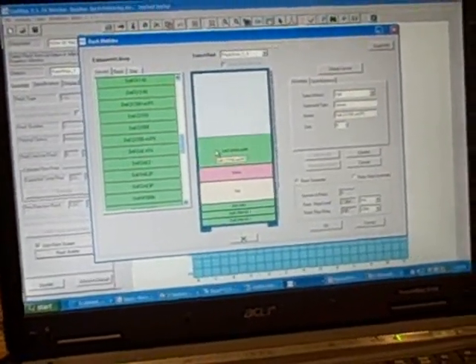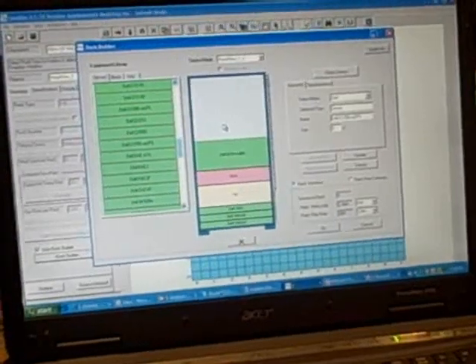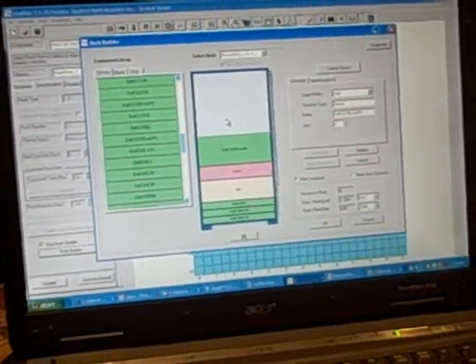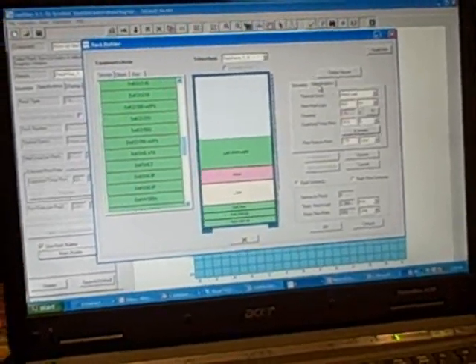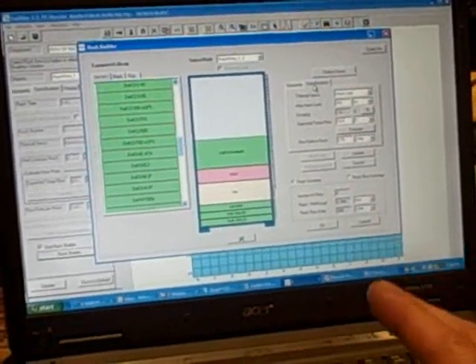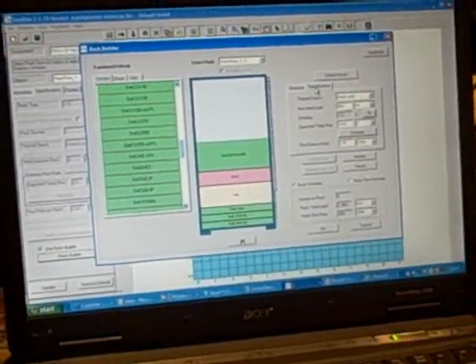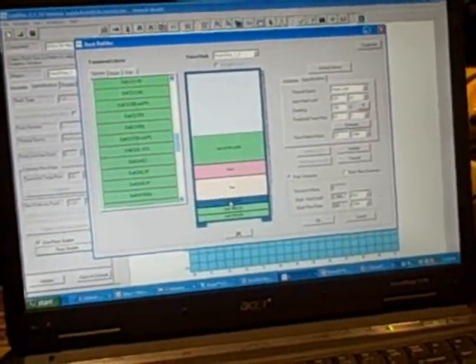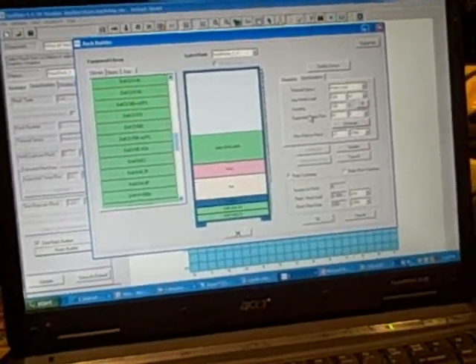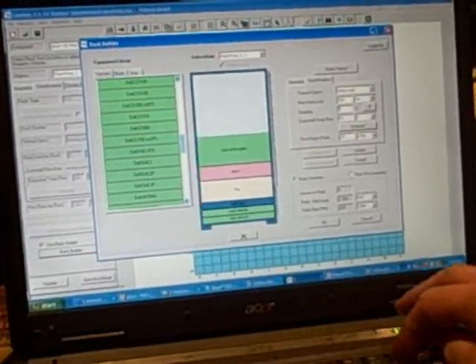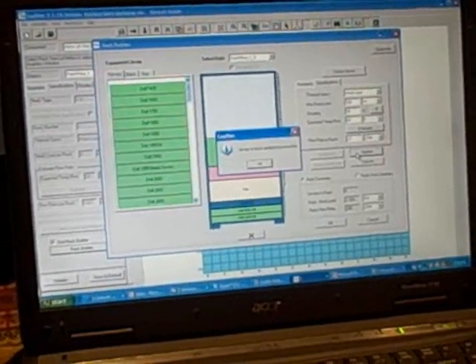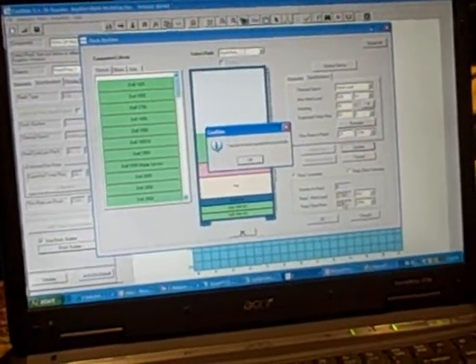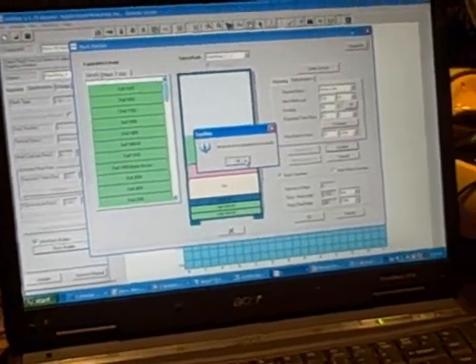As well as UPSs and other things. This is a new feature of 3.2. And it allows you to take the level of detail one step further than we had with average watts. Over here on the right we have the specifications for each one of them. And we've modeled them under worst case conditions. Each one of these library elements has maximum load built into it. However, I can go into a given server, click on it in the rack row, go over and derate it to bring it down to something that's less. Here I'm going to derate by 50% and update and it drops the kilowatts in this particular rack down low. Server and rack is updated successfully.